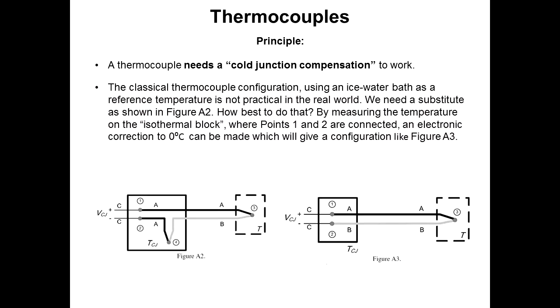So if we take this classical thermocouple configuration using ice water as a reference temperature, that's not practical in the real world because you can't carry that around with you. It's fine for a lab. So we have to have some kind of other reference signal. So you have your two wires that are hooked together at your hot junction. That's what's heated or cooled. The other two are put on this isothermal block. And then there's something on the isothermal block. It could be a thermistor, an RTD sensor, or a diode that's measuring the ambient temperature around it. And that ambient temperature is referenced to 0°C.